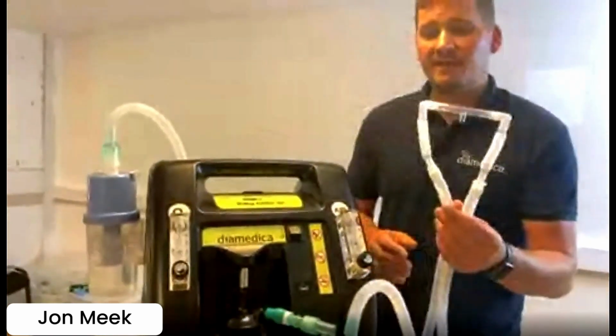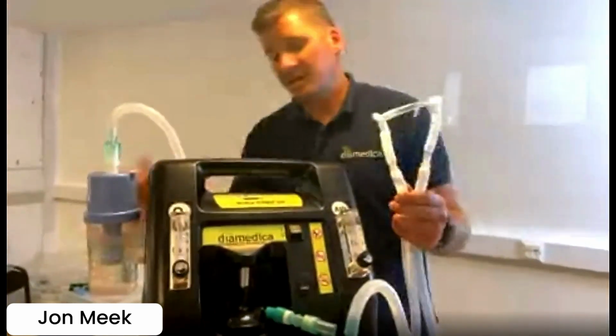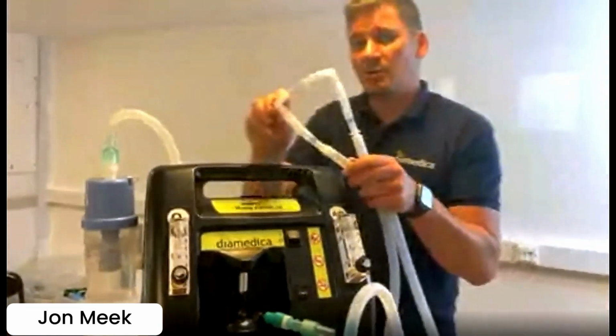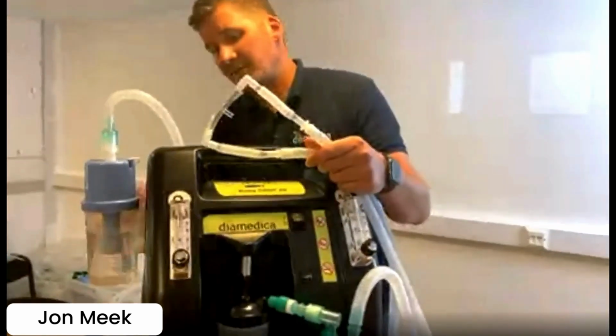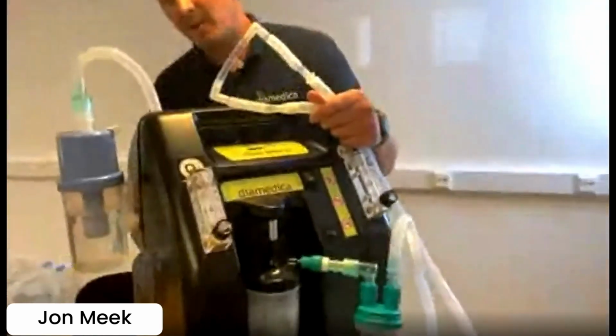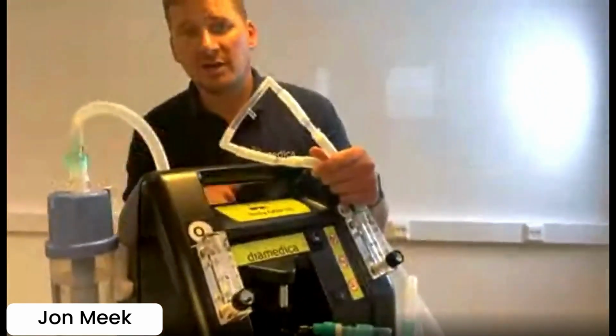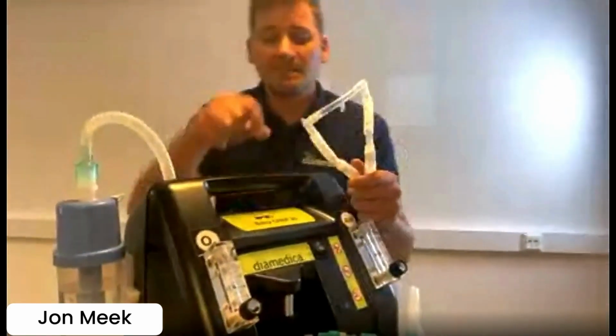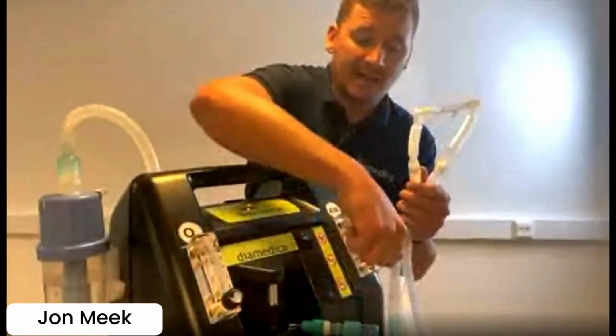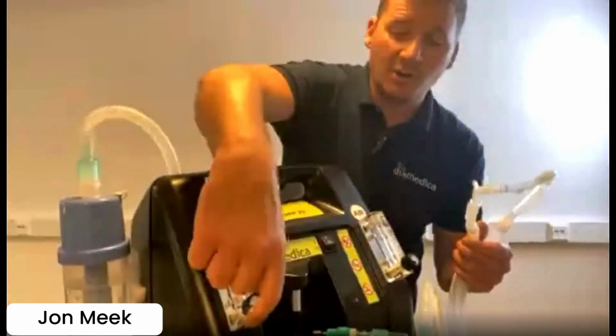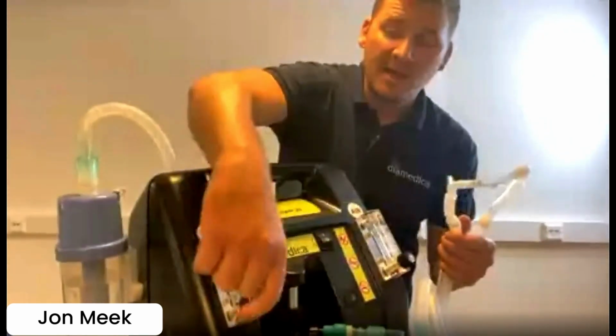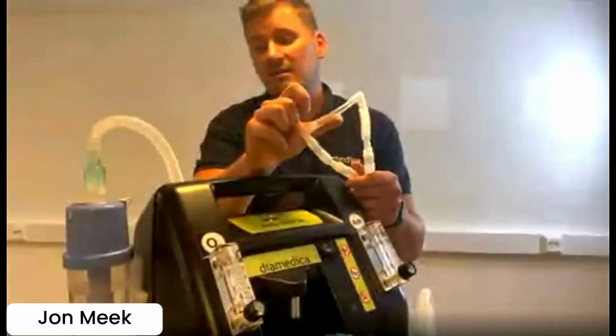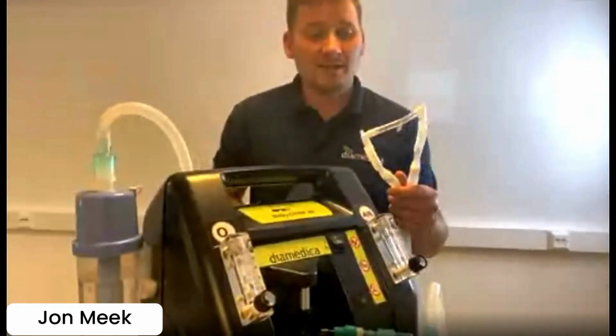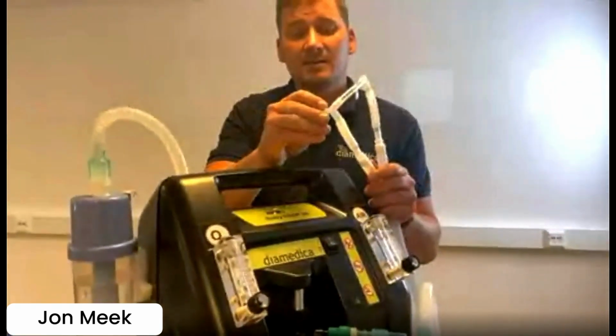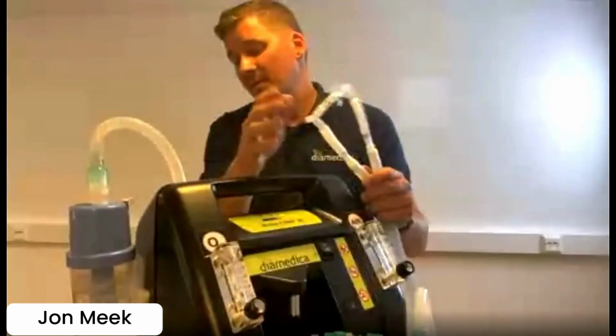So we have the cannula fitted at the moment. You can see we have bubbles in the bubble bottle. If you don't have any bubbles in the bubble bottle, you're not generating the pressure. And this doesn't mean the flow rates have to be higher, because increasing the flow rates is where the issue goes. People think they have to go higher and higher. It tends to mean you either haven't got the cannula fitted correctly, the right size, or you have a leak. If you fix that leak, the bubbles are generated.